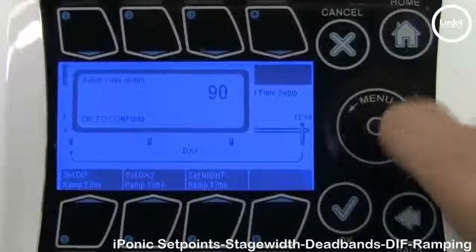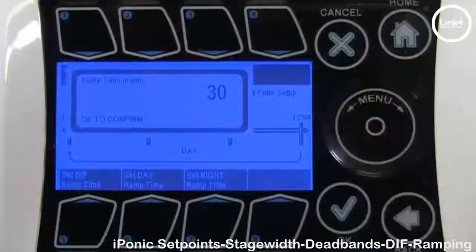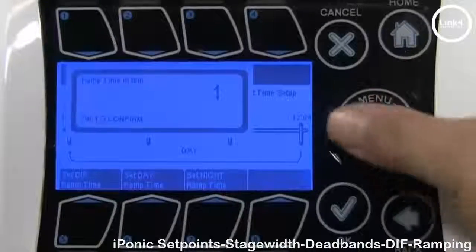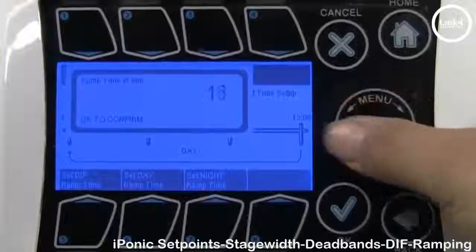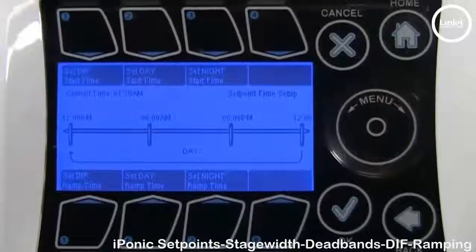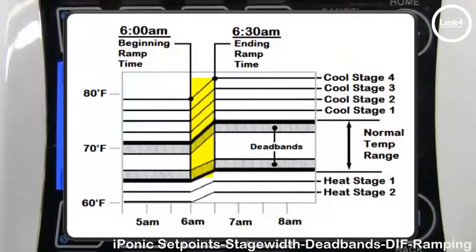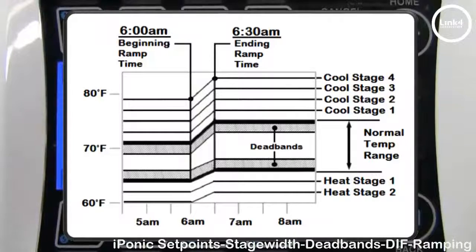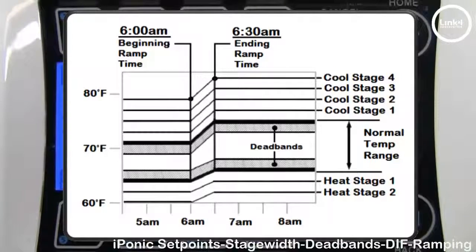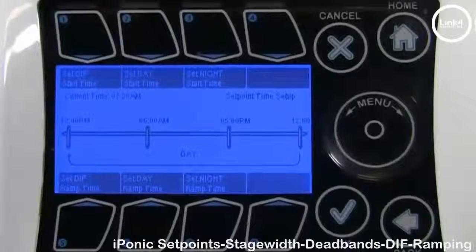We're going to reduce this ramp time to 30 and change all ramp times to 30, so we have a 30-minute ramp time across all set points. Ramping gives you a temperature ramp between the time set points — when each set point time period ends, it ends with a ramp time. This feature allows a smooth temp transition within your grow room and avoids aggressive heating and cooling stages so that plants don't experience temperature shock. It also saves energy, which translates directly into lower operating costs.